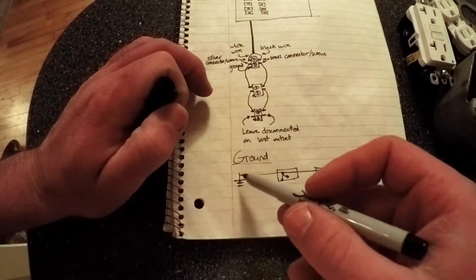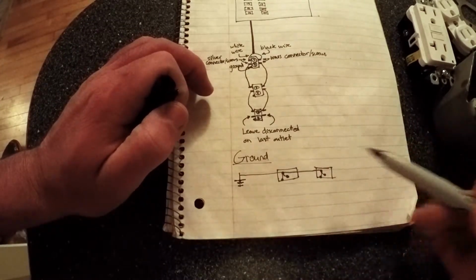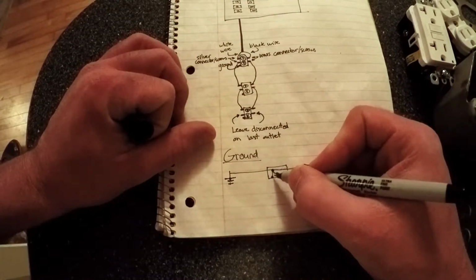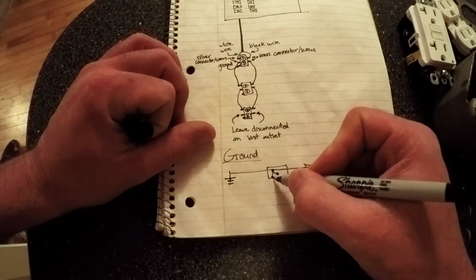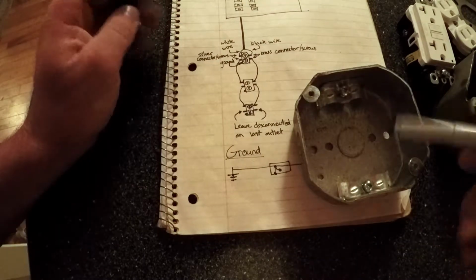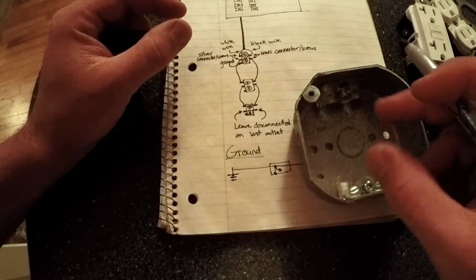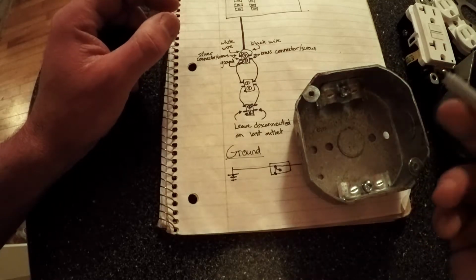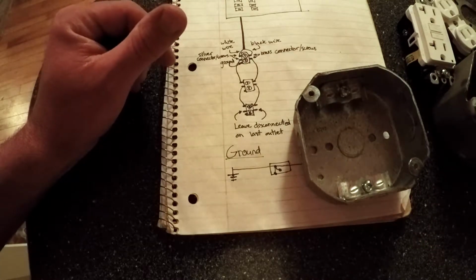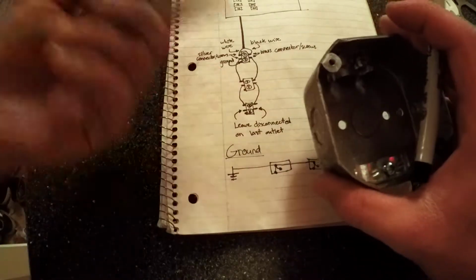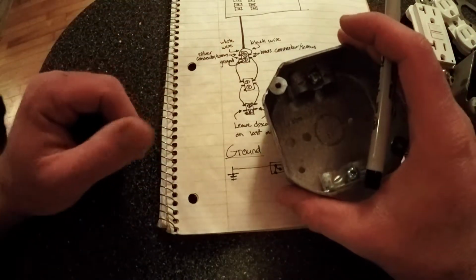Ground wire goes up and into your first junction box here, tee off of your main ground wire. One of the leads is going to go here to the junction box itself. What you can do is either use a fastener, like a small nut and bolt, to clamp it onto there, or you can use one of the screws that's holding it into your stud in the rafter or wherever, and use that to connect it.